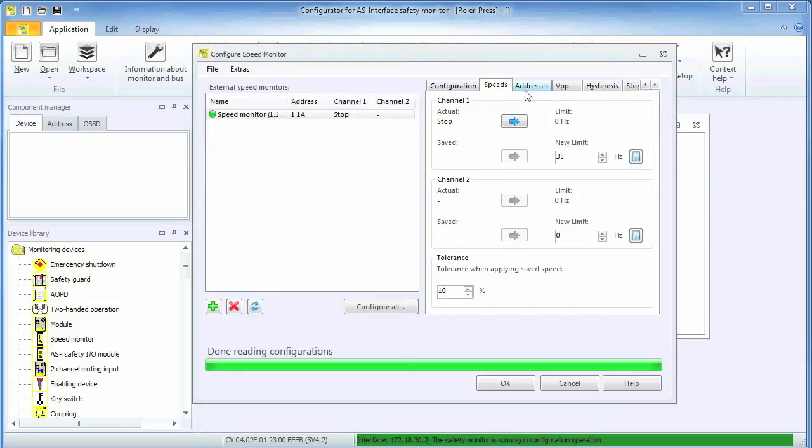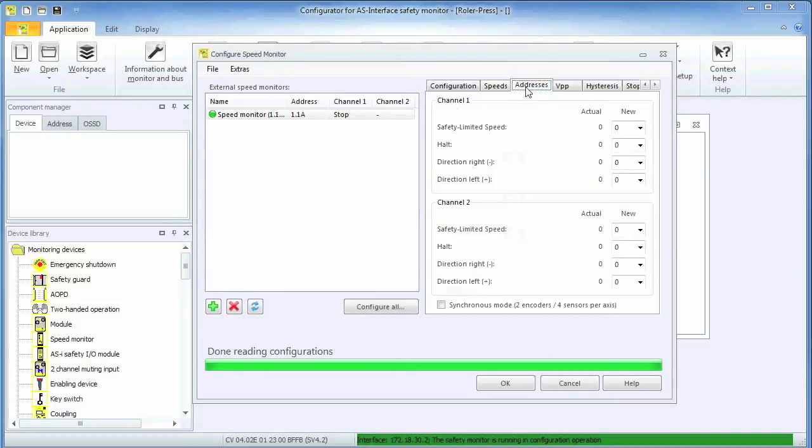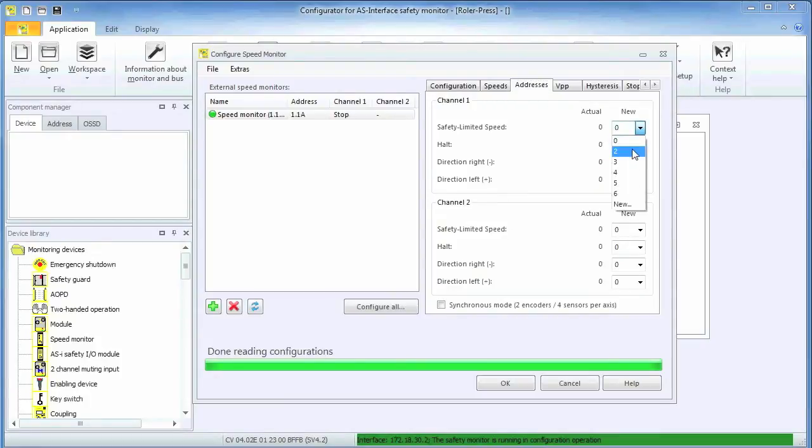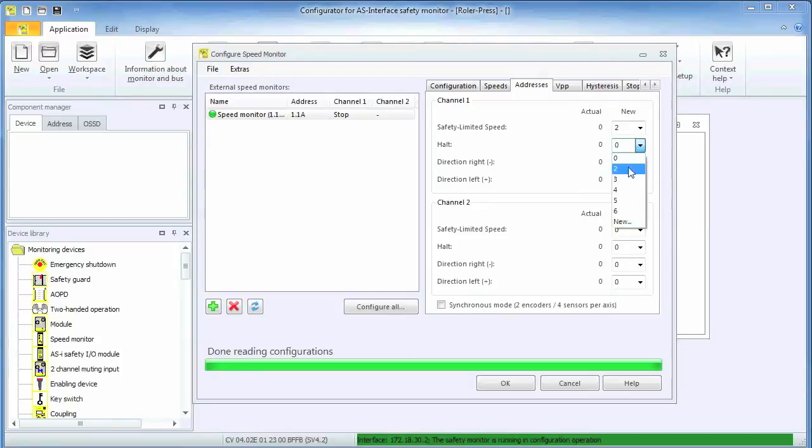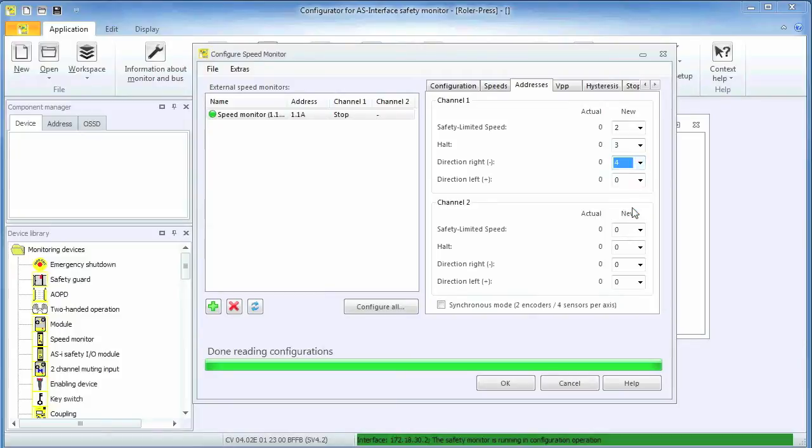On the address tab, those safe addresses representing the safe data we need for the application are configured. Address 2 will signal when the encoder is spinning at a rate below the over speed limit of 35 Hz we defined previously. Address 3 will signal when the encoder has stopped and address 4 will signal when the encoder is turning in the minus direction. For this application example, we are not interested in determining when the encoder is turning in the plus direction and we do not have an encoder connected on channel 2. This is indicated by a zero in those address selection boxes.